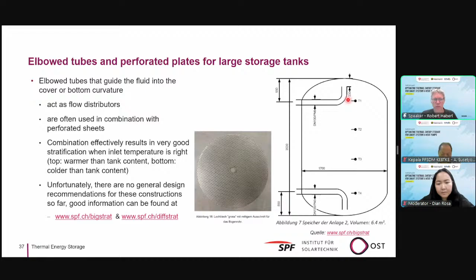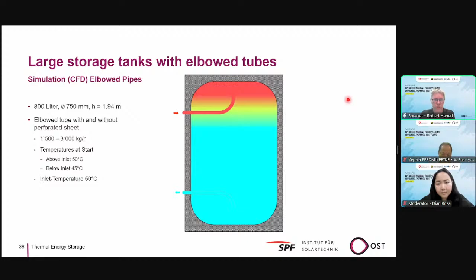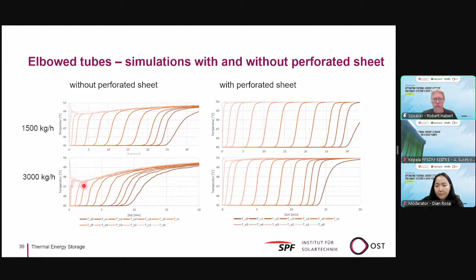There are no general design recommendations, but if you use a perforated sheet, it's almost always good. I show an example here, 800-liter tanks with an elbowed tube that is charged. If you have a perforated sheet, you keep the upper part hot and charge it and raise the temperature in the lower part step by step until you have a fully charged storage tank. If you have no perforated sheet, the temperature drops in the top region of the storage tank, and you have mixing processes that are stronger with higher speed or higher power of the charging.